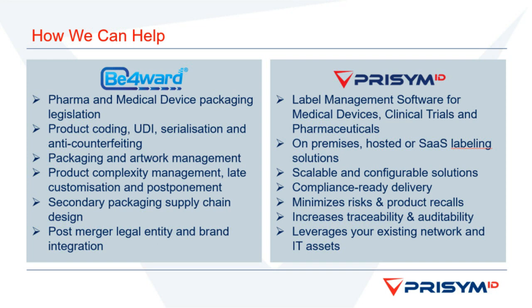Now, the DI forms only part of the UDI. The second part, which is the PI, is what's used to identify a particular instance or product of a product family. And this will consist of typically either serial number and or the lot number, whether you're identifying individual components or part of a lot run. It will include the manufacturer and or the expiry date, and for items which contain software will also contain the software identification, so it could be a version of the software.